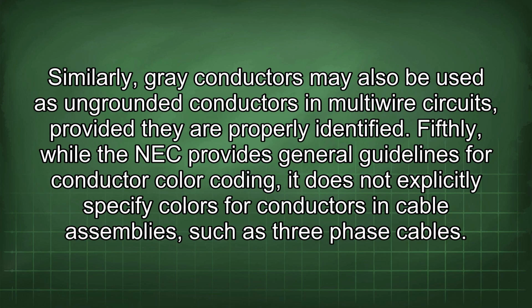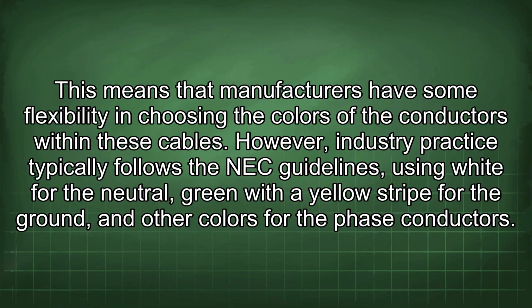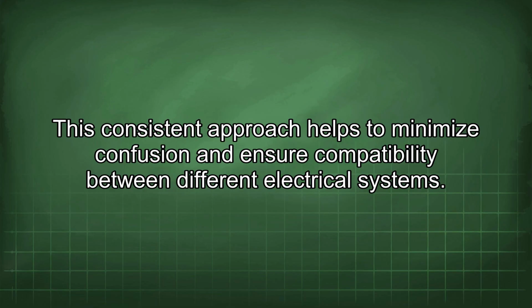Fifthly, while the NEC provides general guidelines for conductor color coding, it does not explicitly specify colors for conductors in cable assemblies such as 3-phase cables. This means that manufacturers have some flexibility in choosing the colors of the conductors within these cables. However, industry practice typically follows the NEC guidelines, using white for the neutral, green with a yellow stripe for the ground, and other colors for the phase conductors. This consistent approach helps to minimize confusion and ensure compatibility between different electrical systems.